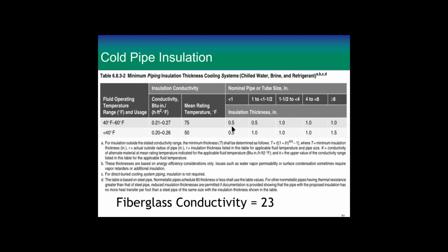This really comes into return pipe and some condenser piping and stuff. But anyway, if you wanted to, you could meet the code without doing it, but you would take a chance that you would have some problems with sweating, etc. But the reason it's there is we could not justify the cost of insulating that pipe on a pure energy basis. The amount of heat we lost out of that pipe was not justified by the cost to cause us to have to insulate.